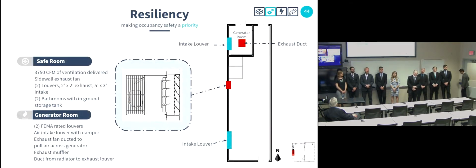Ventilation to the safe room is provided from 2 louvers. One big one on the south end is an intake louver, and an exhaust fan over a second louver towards the north end adjacent to the bathrooms. The generator room is served by 2 louvers, an intake and exhaust louver on the exterior of the building. The exhaust air is ducted from the face of the radiator into an oversized duct to the exhaust louver on the exterior. This duct is oversized to account for the fact that the emergency generator's radiator fan is not going to have a high static pressure value.